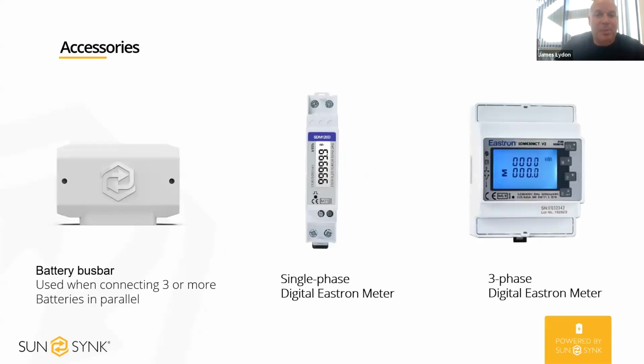Accessories. So we've got our battery bus bar. On the modular kit, the separate items, if you're connecting more than two batteries, so three or more, we always recommend using our battery bus bar. If you've got a job where there's 10 batteries, you would probably need two bus bars. You've got your main battery to inverter leads into the main battery, and then you would use the parallel leads into the next one. But if you imagine there's six batteries, with the inverter connected to the main battery and the rest all daisy chained, those batteries are going to go out of balance quite quickly.